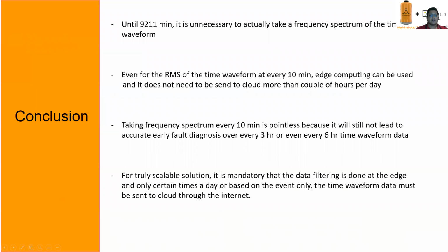So to conclude, it is really unnecessary to take waveform data every few minutes, as it neither increases the fault diagnosis capability nor is efficient from the perspective of power, data cost, or cloud computing cost.